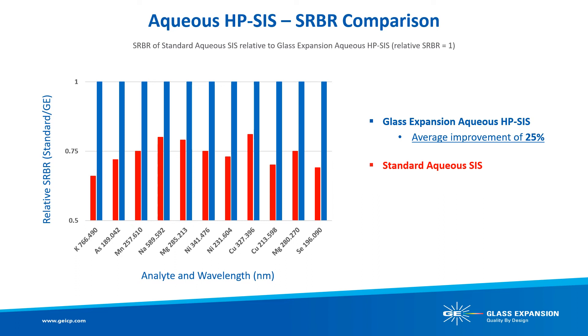The best indicator of analytical detectability for ICP-OES using a solid-state detector is the signal-to-root background ratio. Similar to what was observed for sensitivity, the Sea Spray DC nebulizer, TRACE with Helix CT cyclonic spray chamber, and fully ceramic D-torch provide a 25% average improvement in the signal-to-root background ratio compared to the standard aqueous SIS.